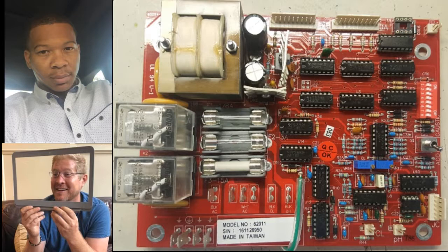Yeah, so that's probably a thing to possibly think about checking with our PM procedure. Maybe we can work together to come up with a test for that, because it sounds like that'd be a pretty big danger if one of those fuses or relays was to fuse in the open or closed position. It could cause an issue. Correct. Very good.